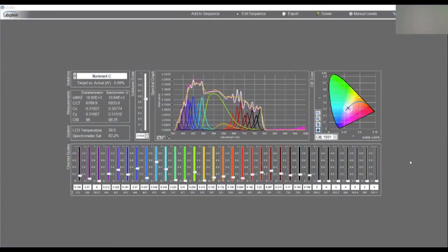Today we want to show you our FT2300 fine-tunable wide-angle field of view flat fielding source and how to load and optimize a source to reproduce a given spectral target. Just to refamiliarize yourself with our system, the gold line is the target spectrum. The white line is how well it's matching. That's the optimization file, which we're going to show you how to produce. And the pink line is a measurement which is done by a spectroradiometer inside the system. So this is the spectral radiance output of the system, and that is showing you the output here on the left.